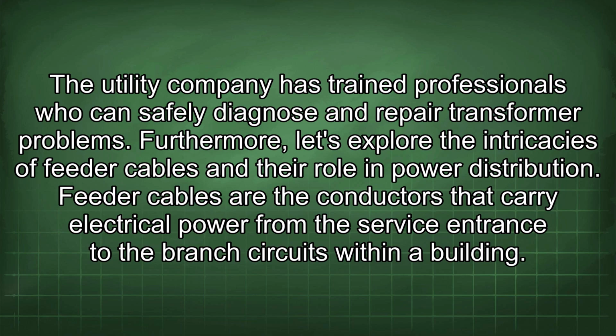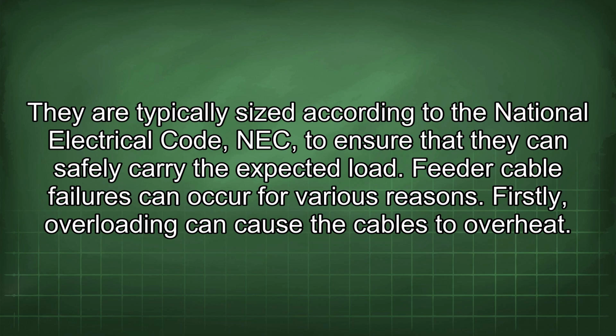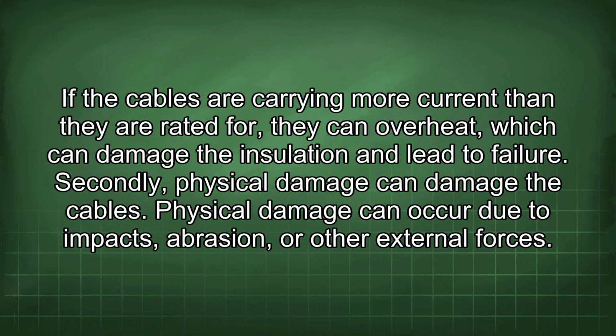Furthermore, let's explore the intricacies of feeder cables and their role in power distribution. Feeder cables are the conductors that carry electrical power from the service entrance to the branch circuits within a building. They are typically sized according to the National Electrical Code, NEC, to ensure that they can safely carry the expected load. Feeder cable failures can occur for various reasons. Firstly, overloading can cause the cables to overheat. If the cables are carrying more current than they are rated for, they can overheat, which can damage the insulation and lead to failure.